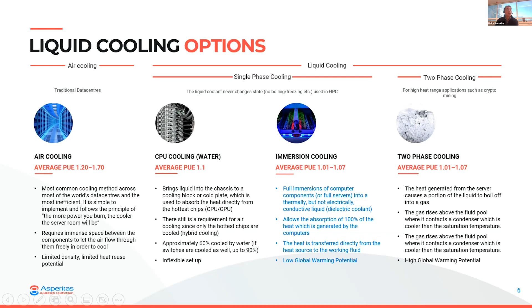There we go. Maybe a little bit more direct - we do immersion cooling slightly differently, and we believe that's the most energy efficient way of immersion cooling. There are no pumps involved. It's a passive system, and I can now explain a little bit how that works from a technical point of view. But altogether, that makes it a very reliable and predictable solution, and from our point of view that's very important - it's one of the elements.